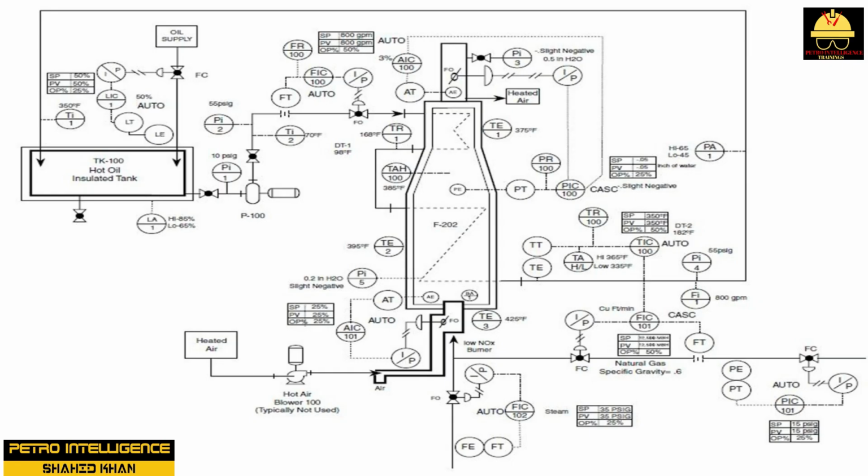F-202 is a clean operating system that keeps excess airflow between 8 and 10%. Ensuring proper air-fuel concentrations is critical to efficient furnace operation because the fuel burns cleaner and hotter. Incomplete combustion reduces heat output, produces waste gases, and creates a potentially hazardous condition as unburned fuel collects in the firebox. Efficient, safe, process heater operation requires a technician to carefully observe and control the combustion process.